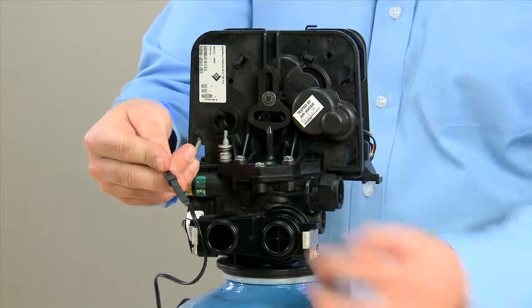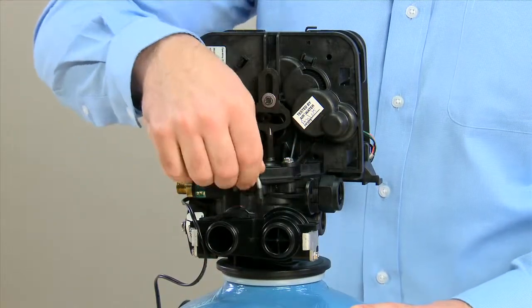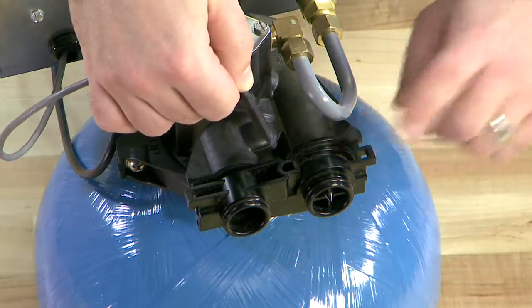We can check for metering by running a magnet across this flat end. Reinstalling it, making sure that it is secure. If we are not registering flow, we need to replace the meter.